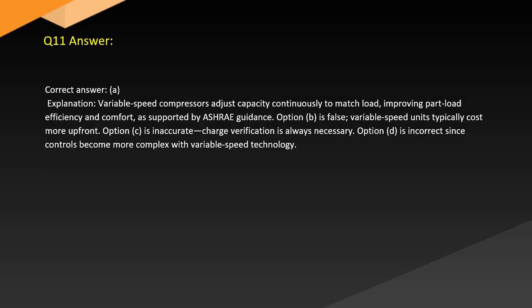Answer. Correct answer: A. Explanation. Variable speed compressors adjust capacity continuously to match load, improving part load efficiency and comfort, as supported by ASHRAE guidance. Option B is false. Variable speed units typically cost more upfront. Option C is inaccurate. Charge verification is always necessary. Option D is incorrect since controls become more complex with variable speed technology.